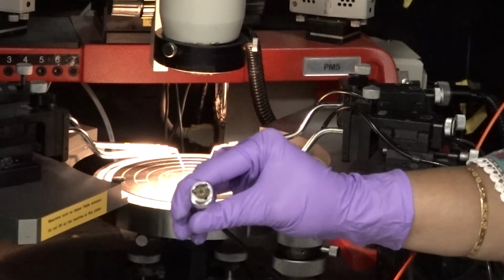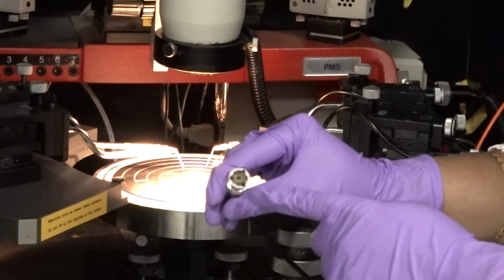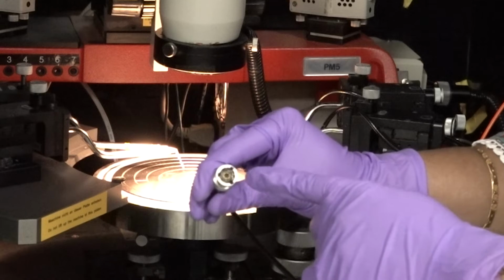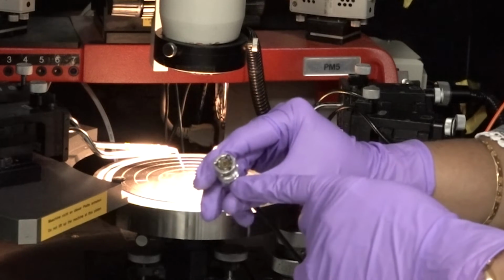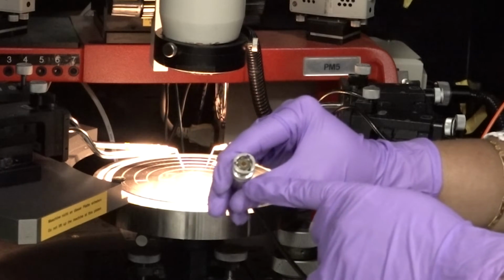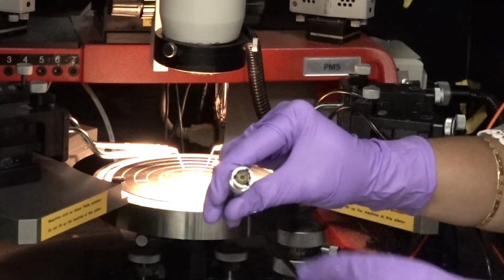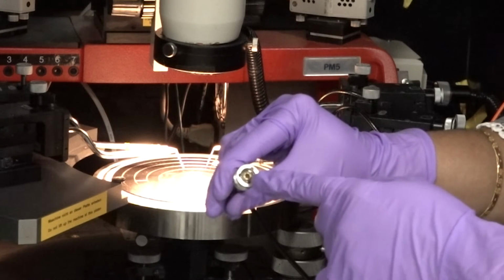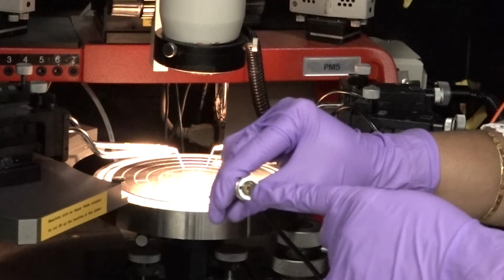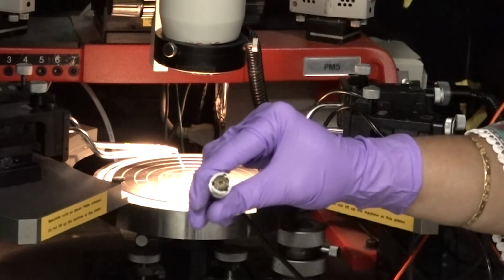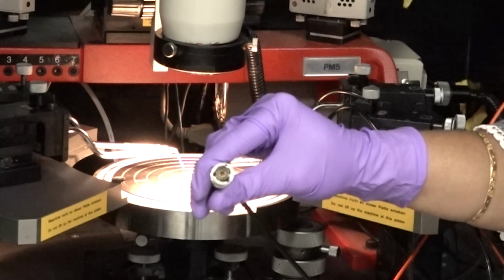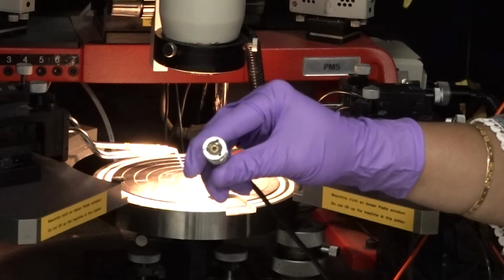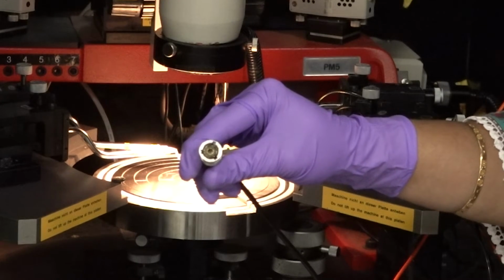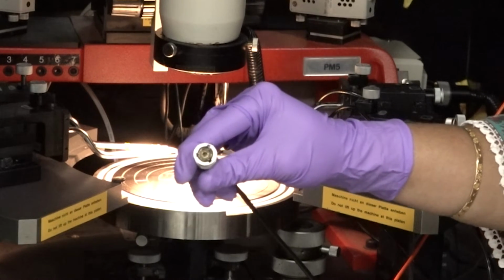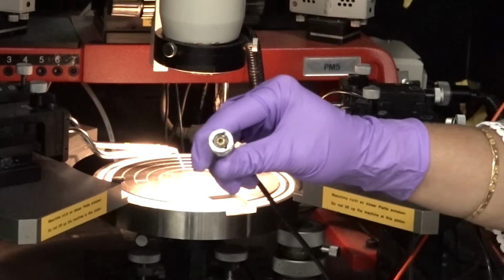So this is the triaxial cable. So we have 3 axes here. So normally in the BNC cable you can see the center pin and the outer body. So the speciality of this triaxial cable is we have a conductive guard ring. So that is the outer golden part, whatever you see from the signal line. So the cable leakage of this triaxial cable, it is basically 1 femtoamp. So this means you can measure range like picoamps, femtoamps of current very easily. So basically this particular triaxial cable is meant for low current measurements.